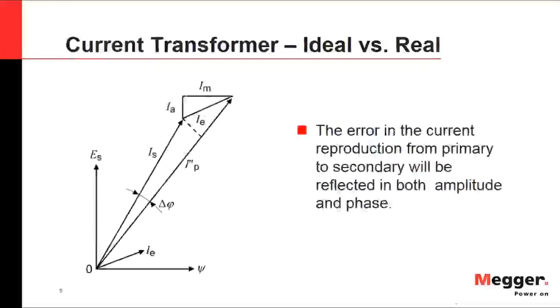Looking at the vector diagram, the error in reproducing the primary current in the secondary can clearly be seen. The electromotive force is 90 degrees apart from the flux. Assuming the primary current is a sinusoidal signal — and all currents, voltages, and magnetic fluxes are sinusoidal — the performance can be illustrated with the phase deviation represented as delta phi in the figure.